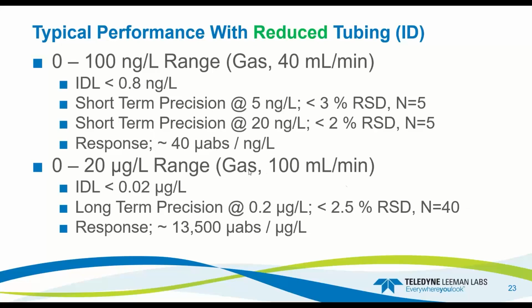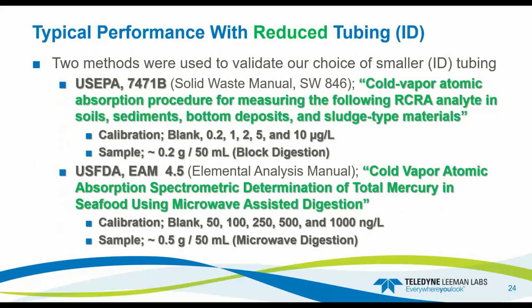If we get into our ppb range, 0 to 20, set the gas flow to 100. The IDL is typically less than 0.02 ppb, maybe around 10, 12, or even 8 ppt in that range. Long-term precision is still really, really good. 0.2 ppb is less than 2.5% RSD, N equals 40, and you have a response of about 13,500 per ppb. Under the normal tubing, this is going to be around 18 or 19,000 in response per ppb. So it's not a huge reduction, but if you look at the math, it's probably exactly that, 33% less, or 67% of what it was before. As I said, it's really linear.